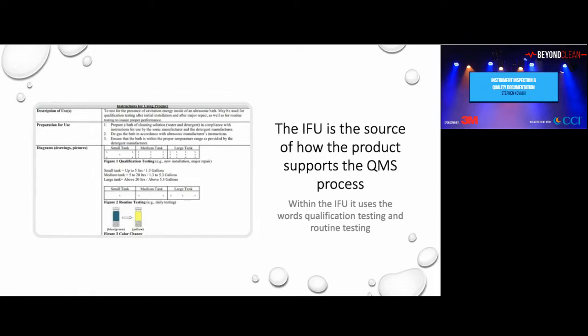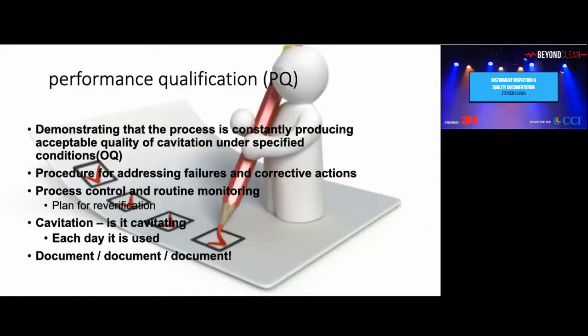It is the Soniccheck. Within its IFU, it uses the words qualification testing and routine testing. That's what it sets up for. It is set up only to check cavitation. So performance qualification, demonstrate that the process is constantly producing acceptable cavitation. So what is the time limit? How are you checking it? Procedure for addressing failures. How do you recertify, re-verify? Check for cavitation each day it's used.